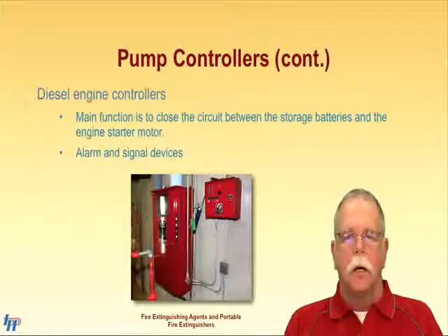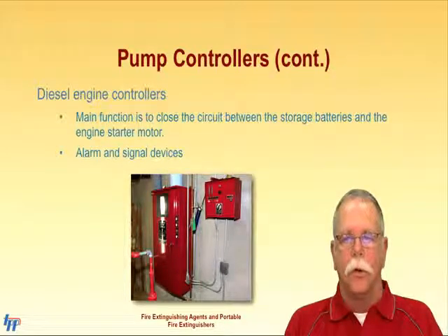A controller for a diesel engine is not the same as a controller for an electric motor. While their tasks may be similar, the way they function is distinctly different. In addition to starting the driver for a fire pump, the diesel controller is a system used to monitor critical functions of a diesel engine and to send an alarm to a monitor if a critical function fails.